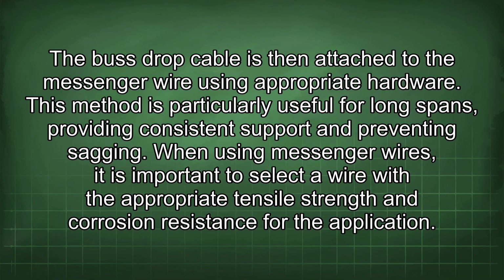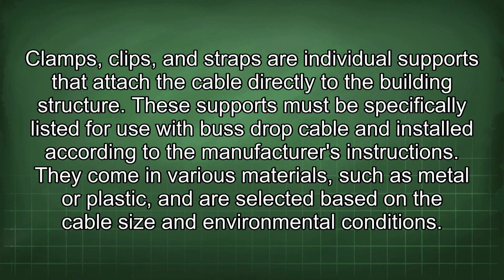Clamps, clips, and straps are individual supports that attach the cable directly to the building structure. These supports must be specifically listed for use with bus drop cable and installed according to the manufacturer's instructions. They come in various materials, such as metal or plastic, and are selected based on the cable size and environmental conditions.